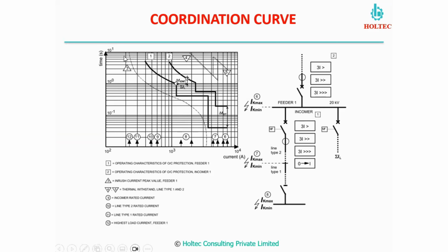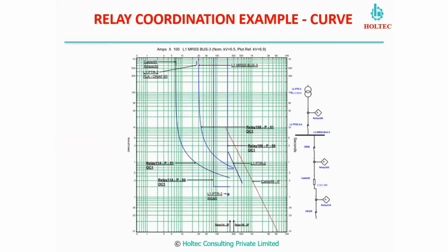It is also giving me the values where my normal starting current or running current should not overlap with these settings. So my setting should be slightly on the higher side of the maximum value of the starting current, inrush current or running load current. In that way, we can properly ensure operational reliability, sensitivity and selectivity. So with this curve, which we can obtain through software, our relay coordination will be almost foolproof. This is the outcome of an ETAP software relay coordination.